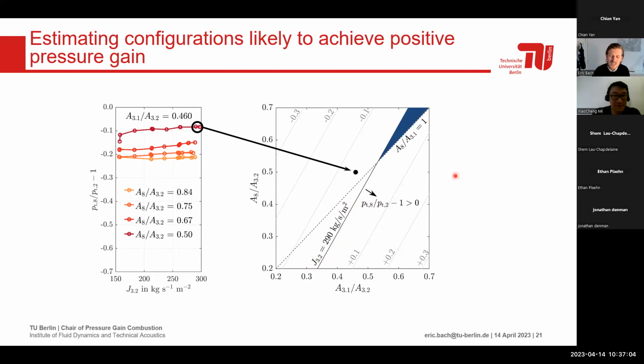And really this leaves only a very tiny design space here. Looking at these values would result in a very open air injector with a quite significant outlet restriction. So depending on the design and the device type, it really doesn't leave a lot of area to play with. What we can also do is use the model to predict the mass flux at which positive pressure gain would be achieved. And in our case, this would be a more than 50% increase from our highest value that we can achieve so far.